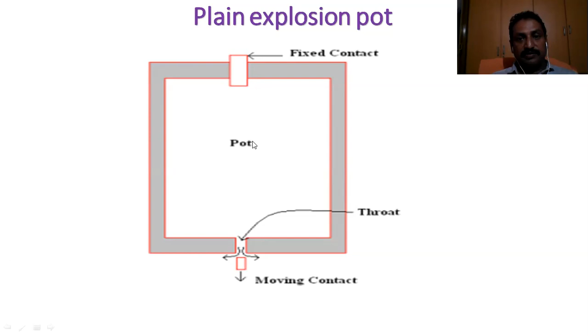Next, the category of oil circuit breaker is the cross jet explosion pot. It is a modification of a plain explosion pot. What we modified here is that arc splitters are used to obtain an increased arc length for a given amount of contact travel, meaning that we want to increase the arc resistance, and similarly the current flow through the arc decreases, and whenever the current flow through the arc decreases, the deionization of the arc increases. So even a small oil can extinguish this arc.